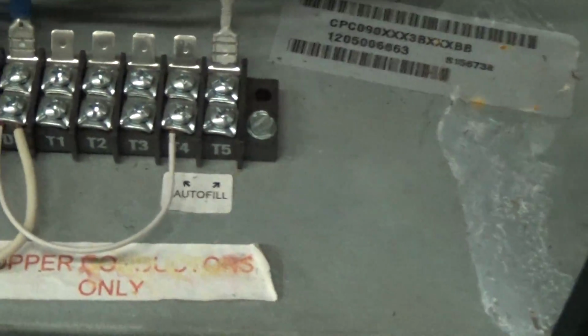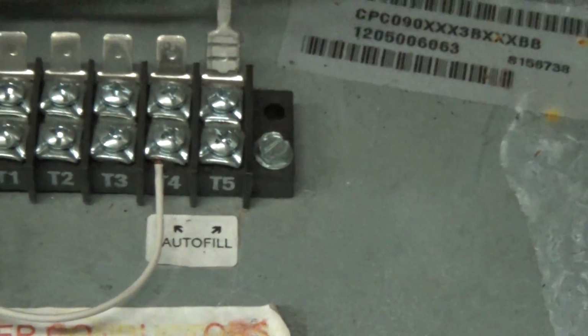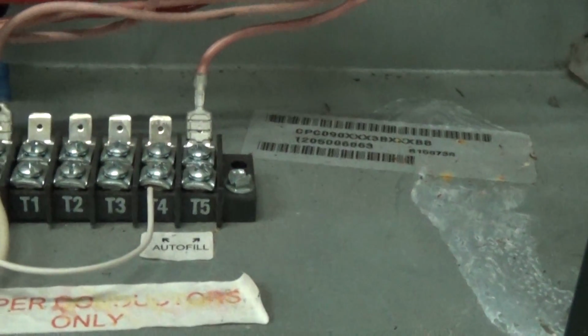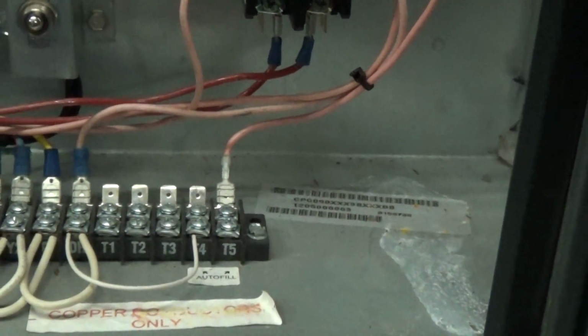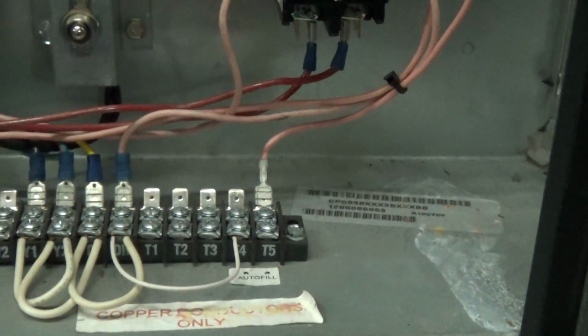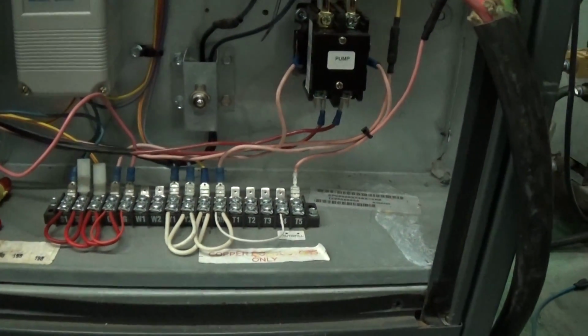Now right here inside the tank, that's the float level switch. You always want to have your fluid level up above that, and on this model that comes back to the terminal strip here, and they actually call it autofill, but you can use it for a couple of different things. There's a timer here, so you don't get any chatter. If you're running straight water, which this customer's not going to do, you can have the autofill terminals tie into a solenoid, so if the fluid ever gets low, you automatically add makeup water. That's not as practical if you need a glycol solution.